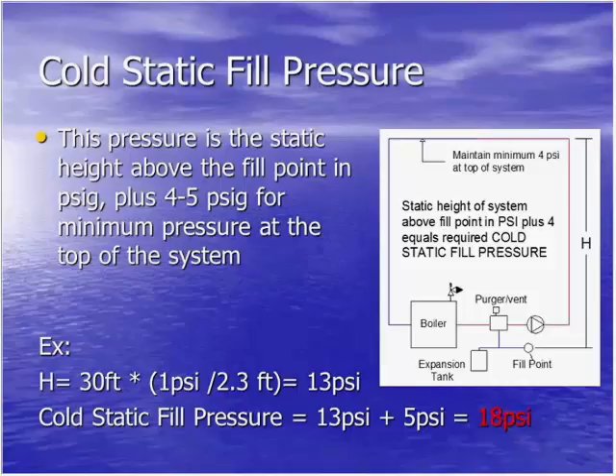The pressure required to push fluid to 30 feet high within that closed loop system is about 13 PSI, because it's 1 PSI per 2.3 feet of elevation. And then you obviously require a positive pressure at every point. So the industry standard is to have at least 4 to 5 PSI of pressure at the highest point. So in this case, the static fill pressure required would be about 18 PSI if the highest point in your system is 30 feet above that fill point. So fairly easy to calculate.